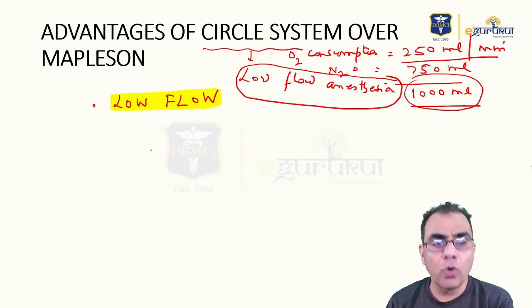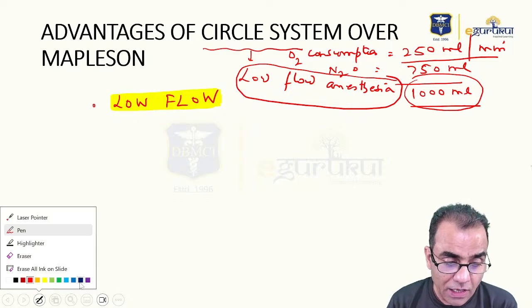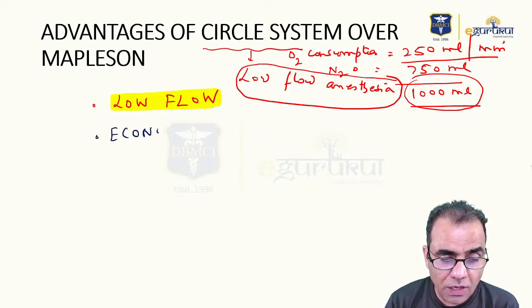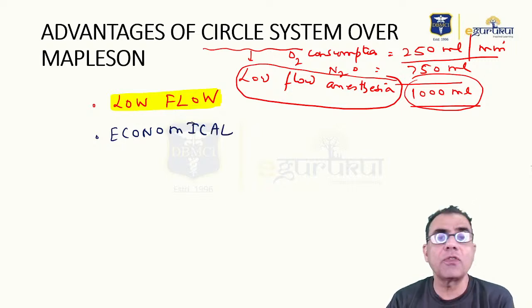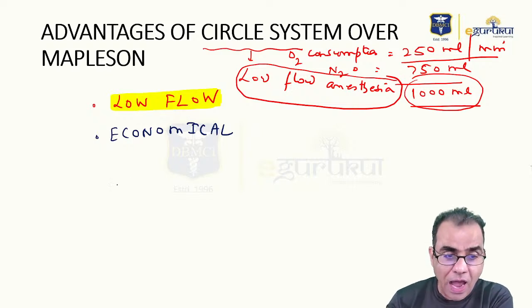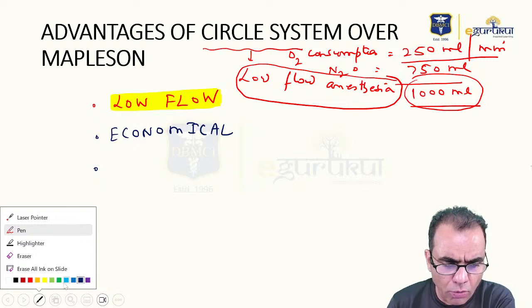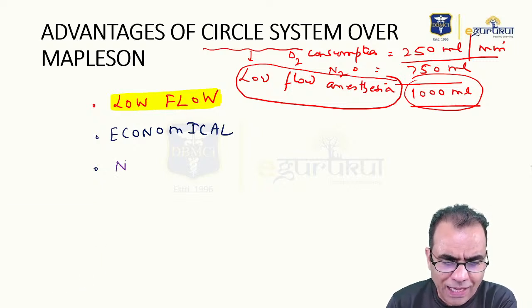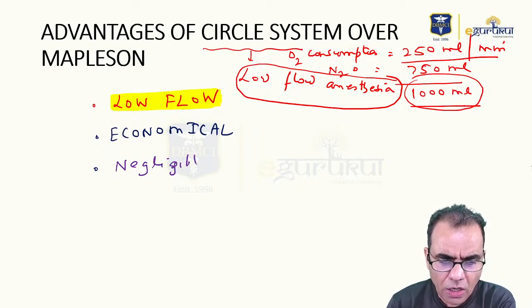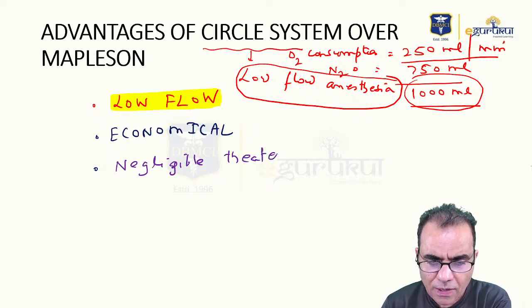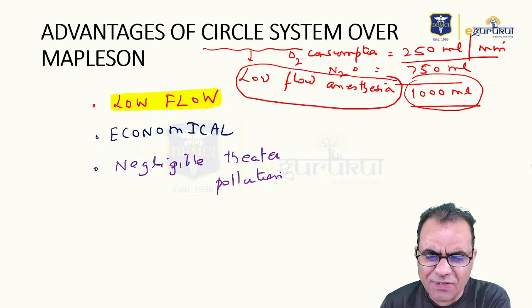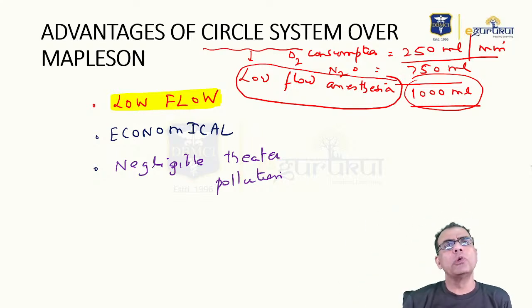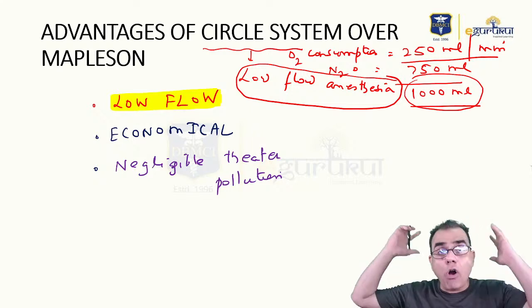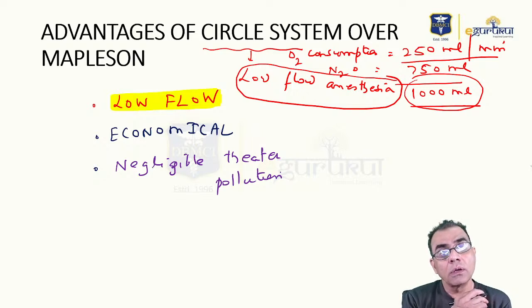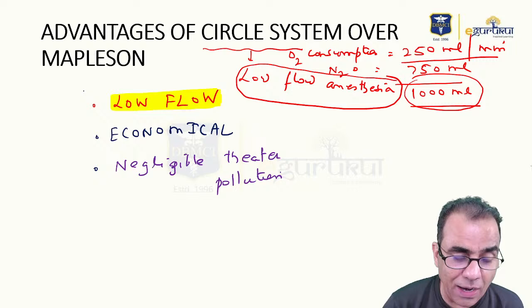So the biggest advantage is low flow. And because of the low flow, obviously, they become very economical. Consumption of gases is so low. So obviously, they are very economical. And thirdly, no or almost no, you can say, negligible theater pollution. Only minute gases which are leaking from circuits or machine may pollute the theater, while with semi-open circuit, all volume is exhaled into the atmosphere. So negligible theater pollution.